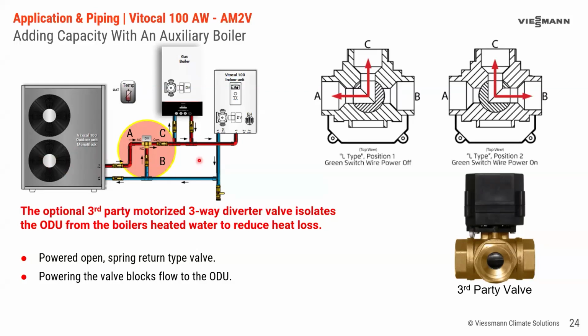And that's fine if that's what the design is for, but you'll have to take into account then your boiler has to be sized for whatever the energy loss is going to be out here, right? Now, it is again controlled by the boiler. So something in the boiler's output, usually it's a pump output, will close this valve so that the water can't go through this way and it bypasses this way, right? So just remember that the boiler's controlling this valve. And these boilers are going to be just an on-off signal, so that's why we're powered open, spring return. And piping it correctly as well, right?